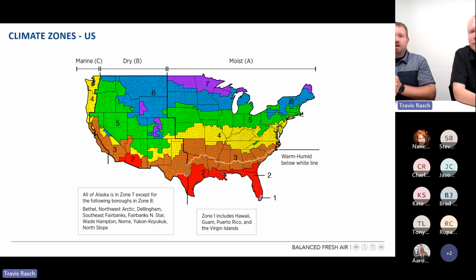I personally have an ERV in my house. I'm located just outside Milwaukee, Wisconsin. We had a stretch this last winter around Christmas time where it didn't get above -10 degrees Fahrenheit, and I just let my ERV run continuously during that time. It's effectively managing that moisture through the defrost cycle, through the materials that core is made out of. We'll talk a bit more about other advantages of an ERV in different climate zones.